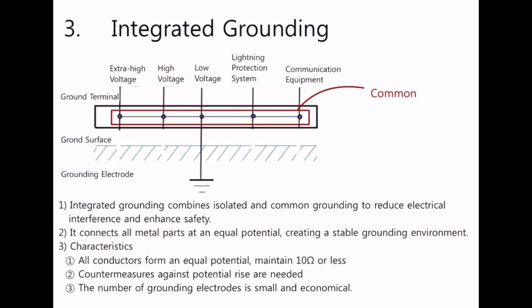Integrated grounding. Definition. Integrated grounding combines the advantages of isolated and common grounding, reducing electrical interference while enhancing safety. It creates a common grounding network by connecting all metal parts that people can touch to an equipotential bonding system. System diagram. The diagram shows all equipment, such as electrical installations, communication equipment, lightning protection systems, water pipes, and gas pipes, connected to a common network.